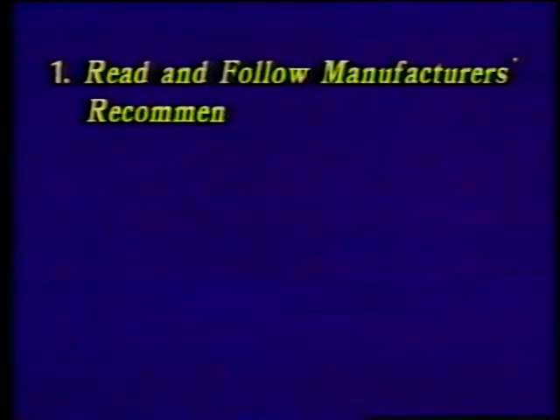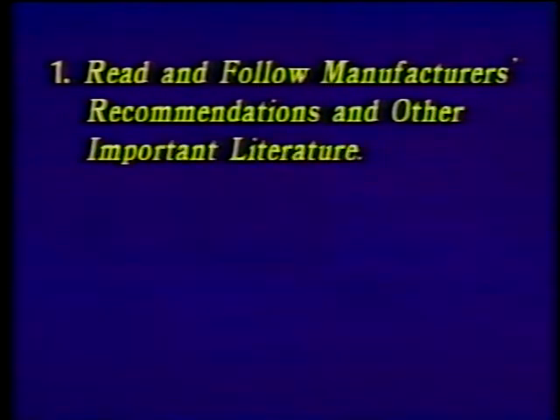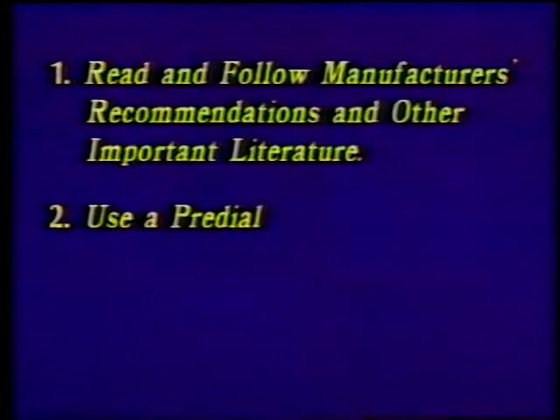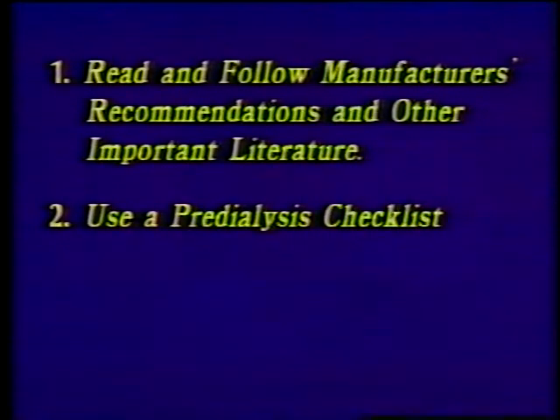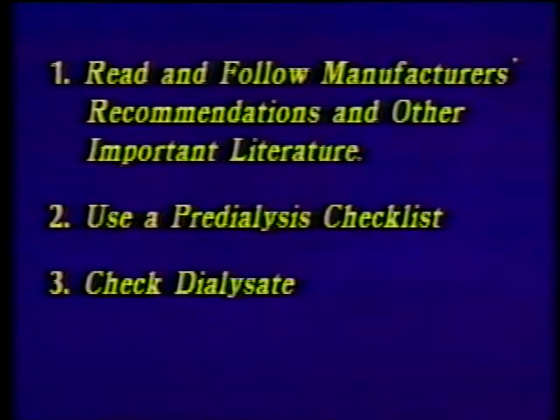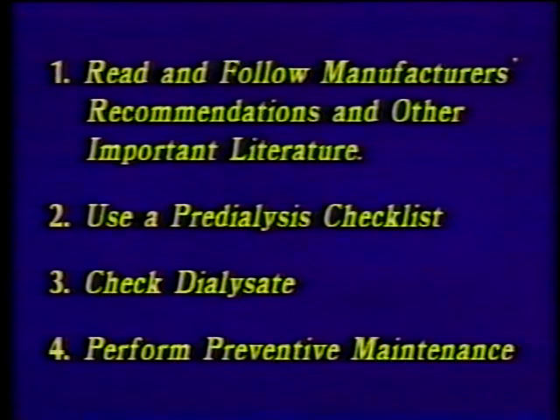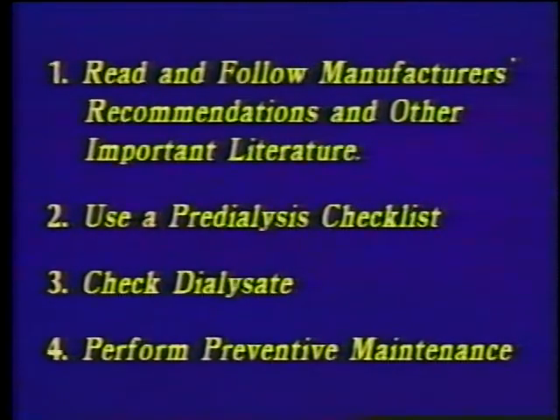For example, if we really are concerned about human error during hemodialysis, we need to become aware of what each of us can do to reduce or eliminate these problems. And that's what the rest of this program is all about. First, we must read and follow manufacturers' recommendations and other important literature. Second, we must use a pre-dialysis checklist. And we must check the dialysate before beginning treatment. And finally, we must perform preventive maintenance on a routine scheduled basis.